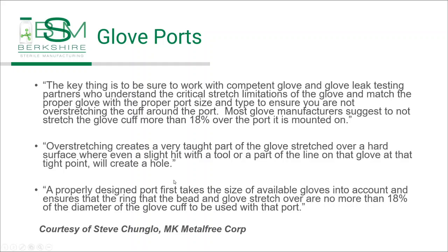These are some comments from emails from Steve Chunglo of MK Metalfree Corp talking about the importance of the fit of the glove with the glove integrity test, with the glove port. A properly designed port takes the size of available gloves into account and ensures that the ring that the bead and the glove stretch over are no more than 18% of the diameter of the glove cuff. So it's very critical that you pay attention to the combination of your gloves and your glove ports.